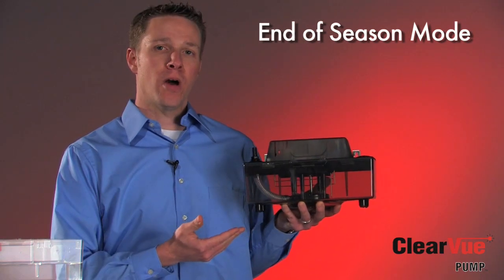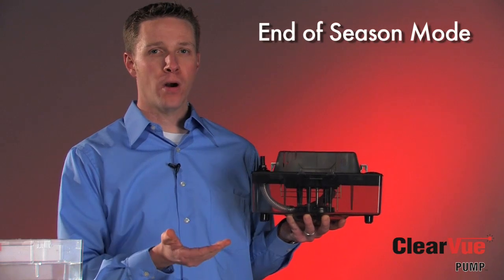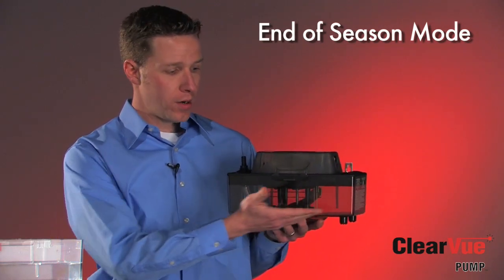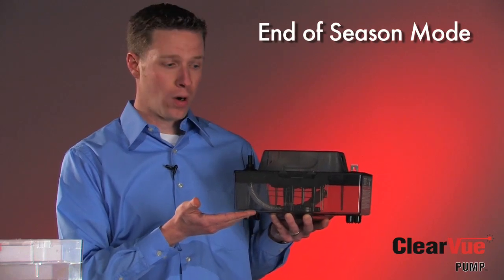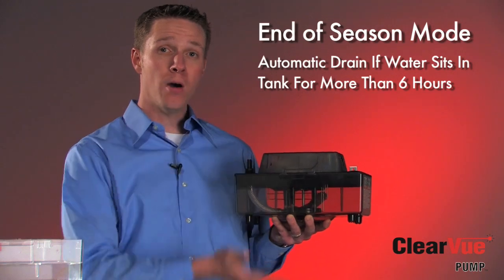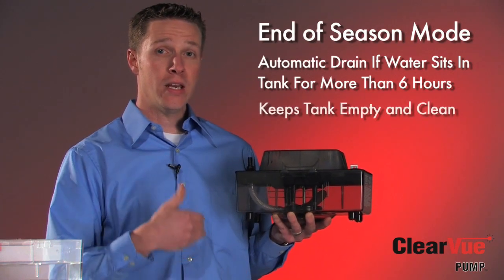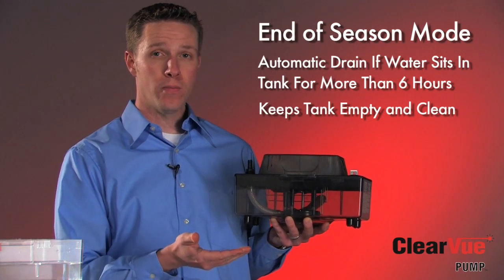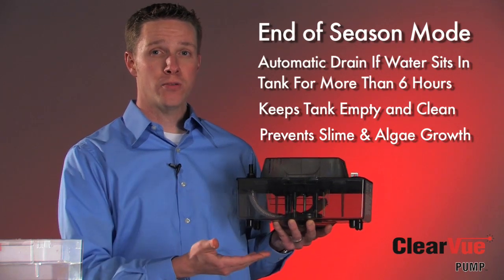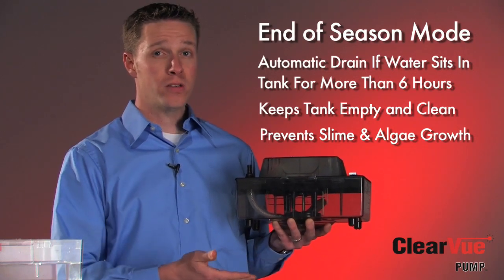The last feature I'd like to talk about with ClearVue is what we call our end of season mode, another part of our IQ technology. Basically, if water has remained in the tank for a period of six hours or more while touching the bottom sensor, ClearVue knows to run a pump-down cycle to get that water out of the tank to prevent any slime or algae buildup inside the tank. With ClearVue, it's almost 100% dry all the time, especially between seasons or periods of not cooling.